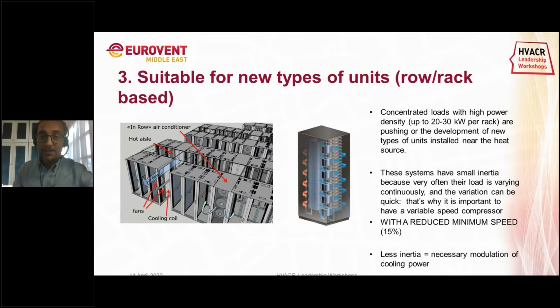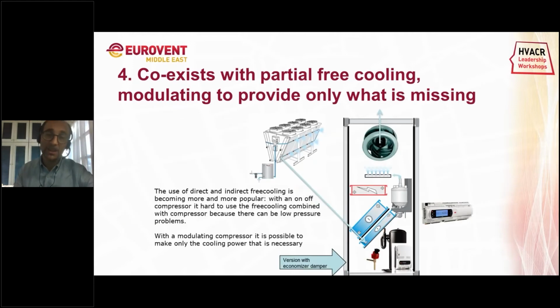Another reason why this technology is becoming important: high efficiency, supply temperature control, low inertia systems. But on top of that, they could be combined with free cooling technologies. Depending on the area where you are standing, there is very often the possibility to have direct or water-based free cooling to take advantage of favorable conditions. Typically, and we've seen the graph before, there is a specific period during the year in which outdoor air temperature is low enough to run in free cooling mode. Very often there is a threshold that will trigger free cooling mode compared to compressor-based mode. Normally, because an on-off compressor cannot modulate, as a consequence you need to select between free cooling mode and compressor-based mode.